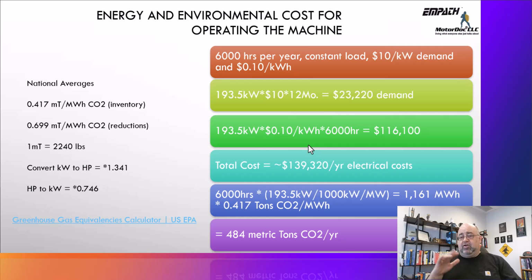Now if I have varying loads, I can put that in there, but for our purposes I'm going to keep it simple. So if I take a look at that and convert it over to megawatts, that comes out to 1,161 megawatt hours to operate that electric motor per year, times 0.417 metric tons of CO2. That is 484 metric tons CO2 per year to operate that machine.